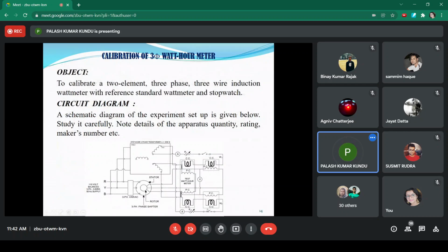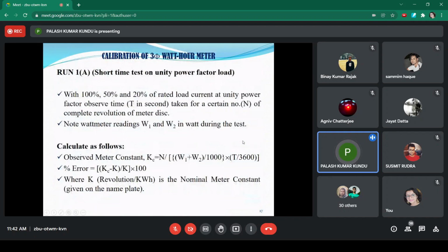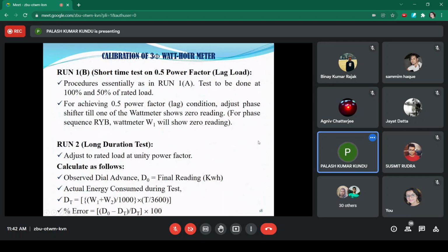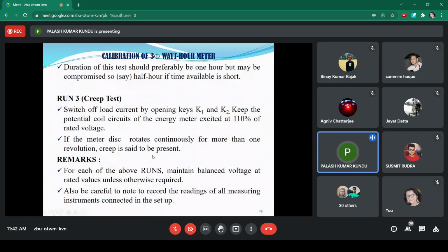This switch should be in the off position, so that there is no flow of current to the current coil of both the meters, that is, the wattmeter as well as the energy meter. Under this condition, the disc rotation that is observed is due to creep action. If the meter disc rotates continuously for more than one revolution over 24 hours, the creep is said to be present, otherwise not.